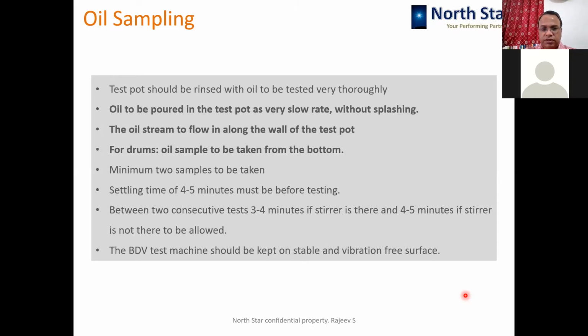Okay, so there are some points I mentioned over here on how it is to be done, and accordingly that should be taken care of. Of course, the sample should not be taken in mineral water bottles. They are to be proper, either glass bottles or syringes or stainless steel bottles. Ideally, those bottles are to be vacuumed and flushed with dry nitrogen, and then the oil sample is to be taken. But it is followed very, very rarely.